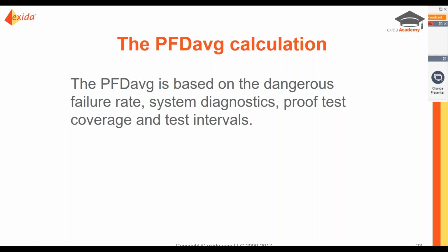The manufacturer should not give you a PFDavg calculated number for their device alone, unless the device is an entire system.